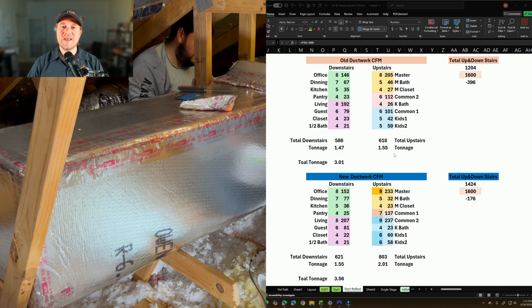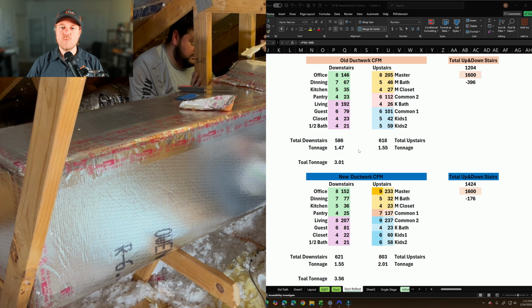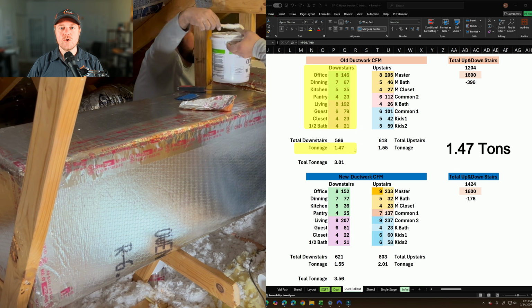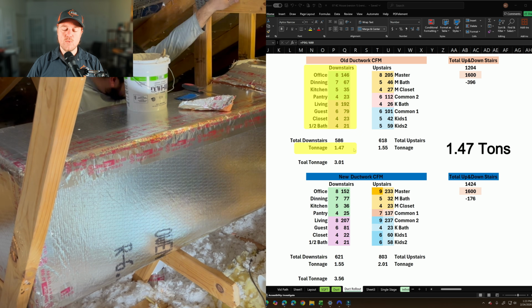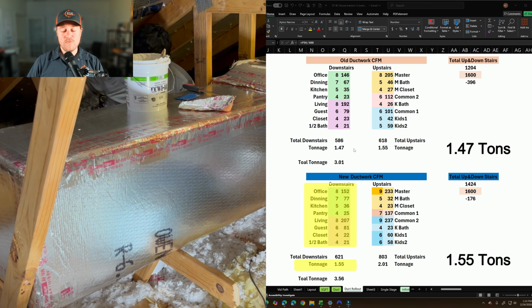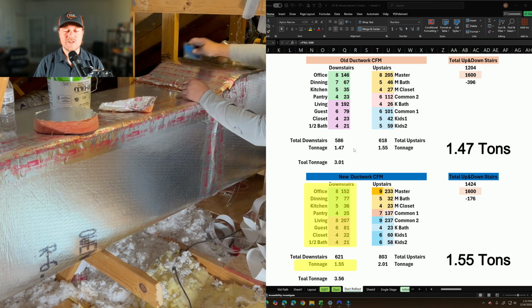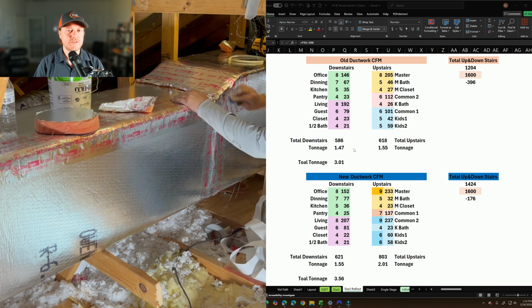Alright, back to our old downstairs ductwork. You can see that we were getting 1.47 tons of airflow out of the downstairs vents. Now we're getting 1.55 tons of airflow. Overall, not all that big of an improvement. That's probably due to the system pushing 200 CFM less.